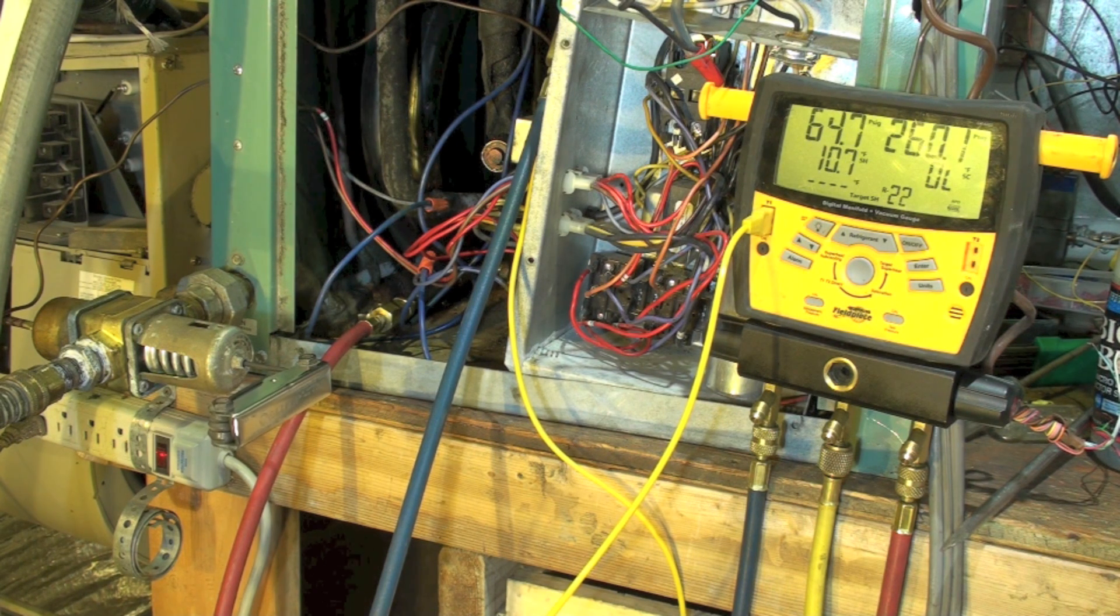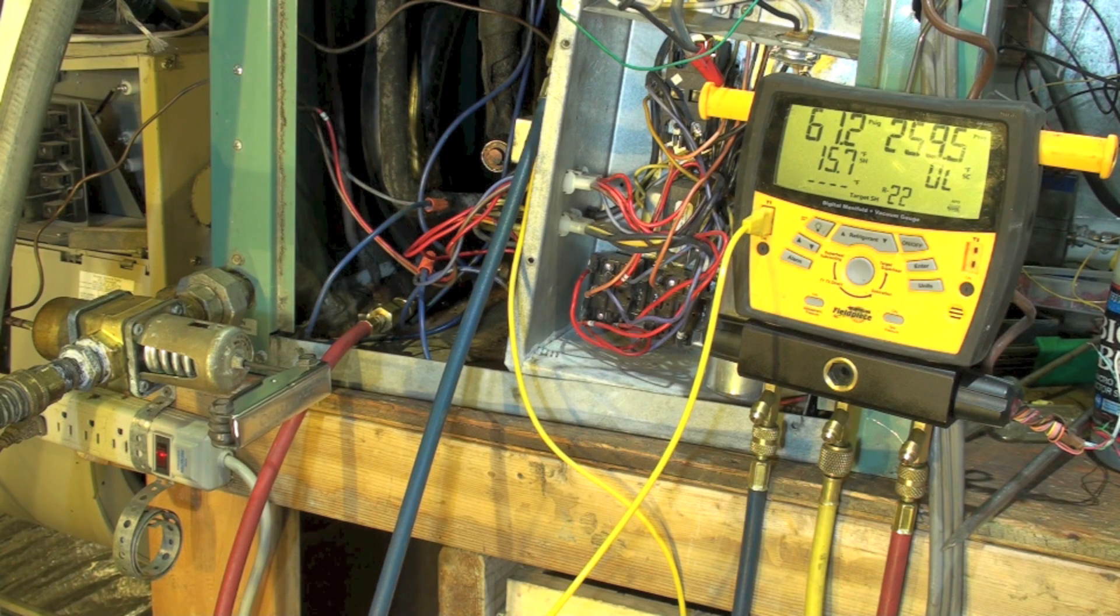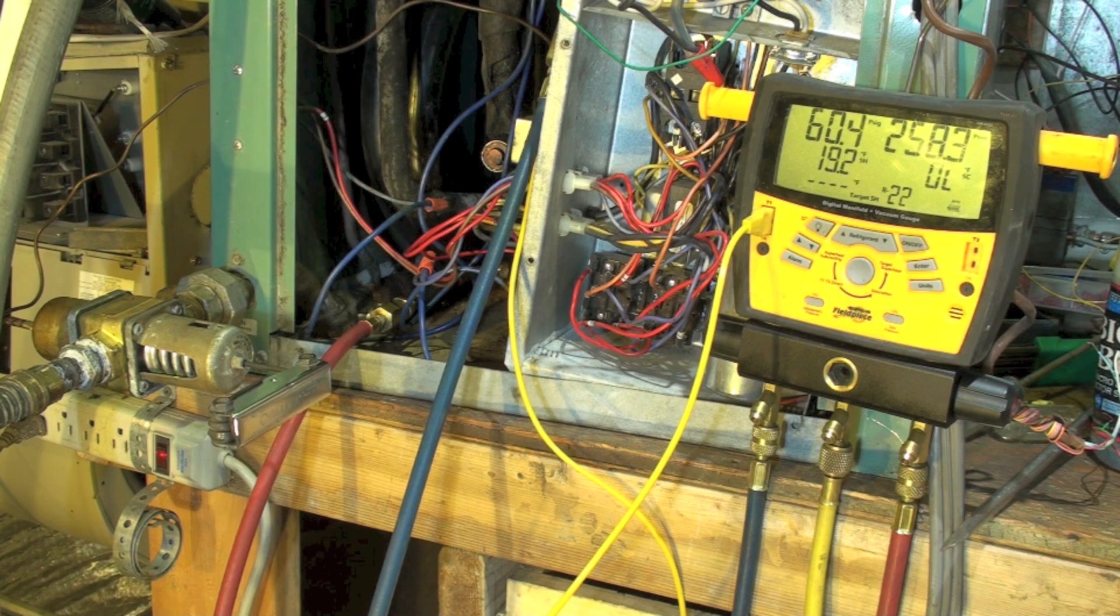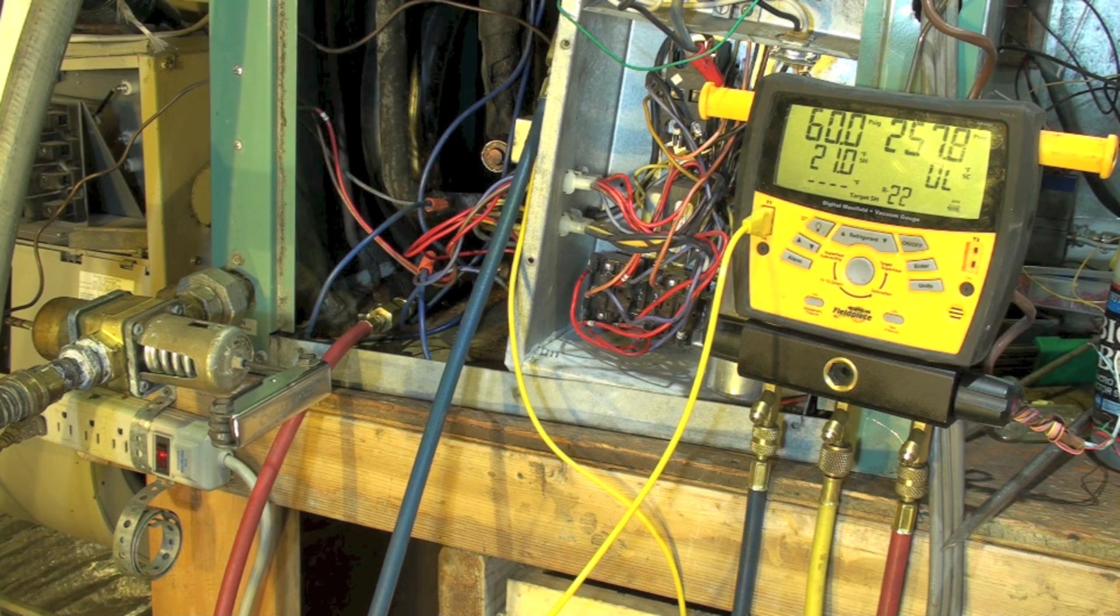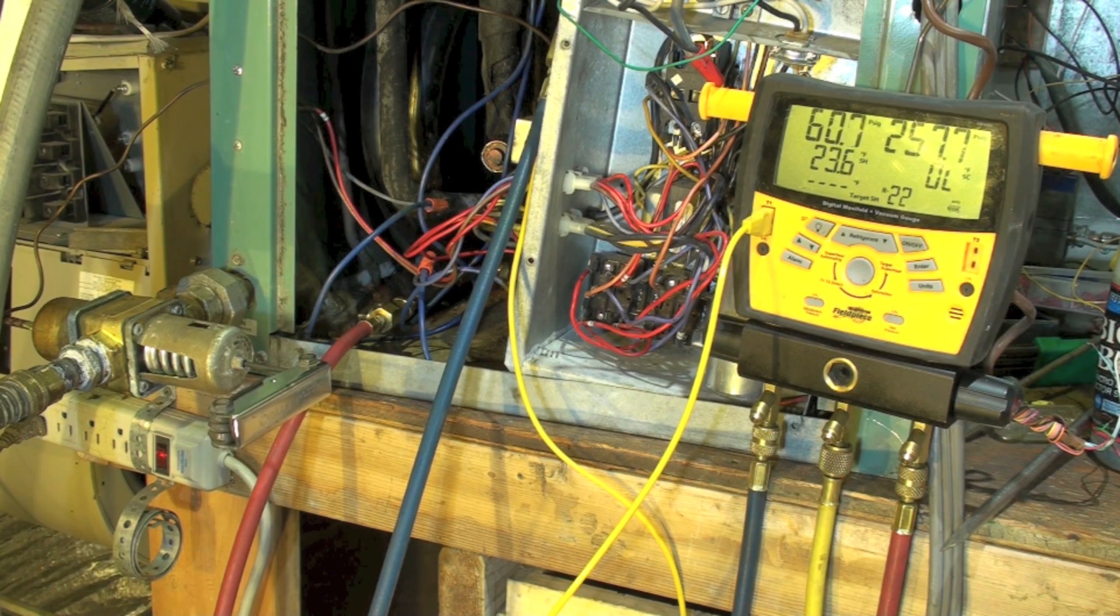Now you can see an immediate drop in the head pressure. You also see a drop in the suction pressure, and that's normal because this is a fixed orifice device unit. There's actually about four cap tubes up there. Now my suction pressure kind of dropped in the toilet, superheat went way up. We'll probably adjust a little bit from there.